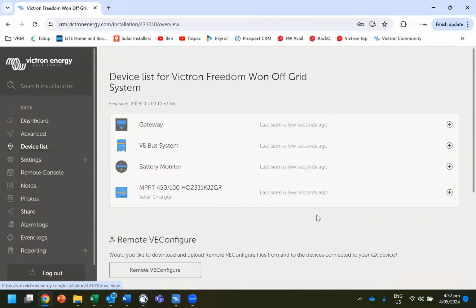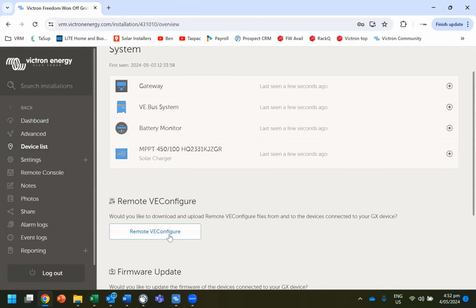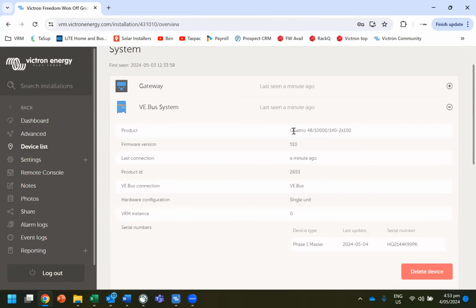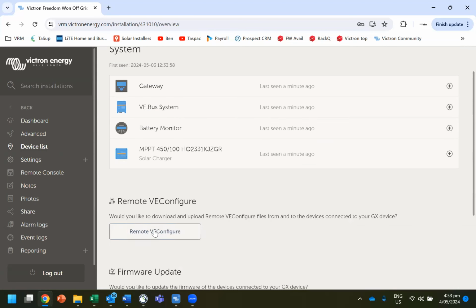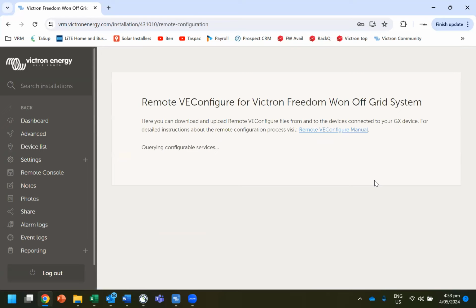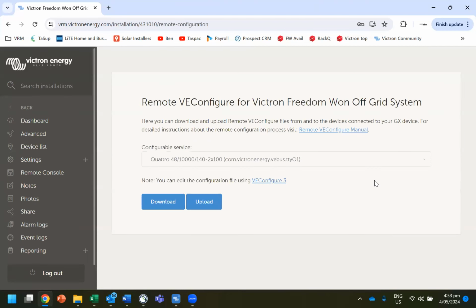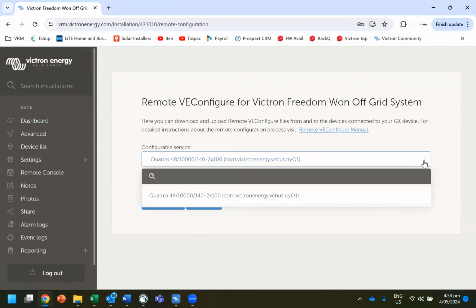So if I go back to the device list, now I'm going to look at VEConfigure. Now VE is the VE.Bus system, Victron Energy Bus. It's configuring the inverters that are on the system. So I click on that, and again, it's going to scan for all the devices and find what's on the bus, and there it is. That's what we've got. So we can download that software, and then we can get into it using VEConfigure.